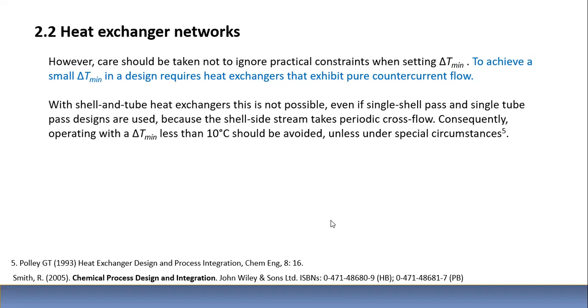Pure countercurrent flow: with shell and tube heat exchangers this is not possible, even if single shell pass and single tube pass designs are used, because the shell side stream takes periodic cross flow. Consequently, operating with delta T minimum less than 10 should be avoided unless under special circumstances.